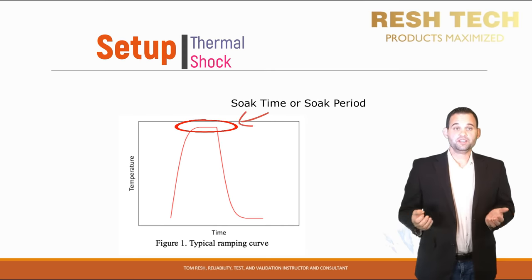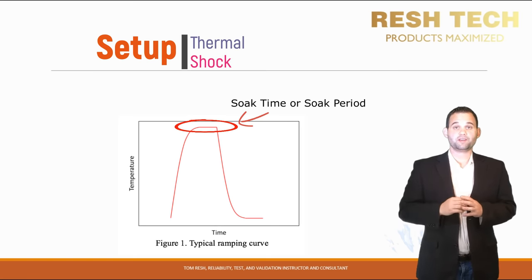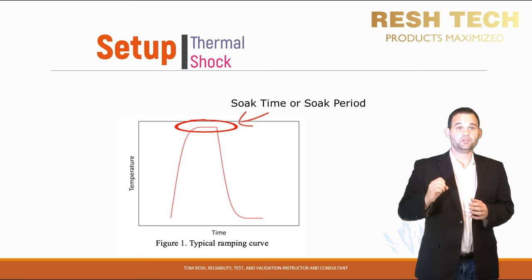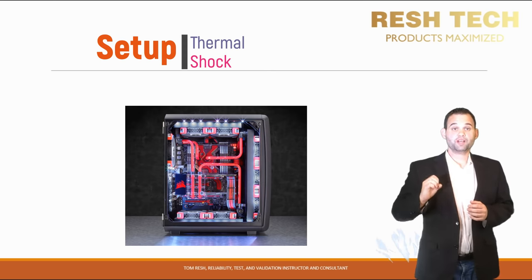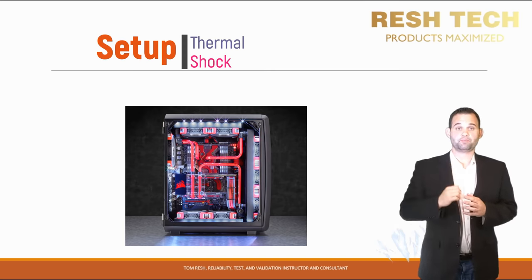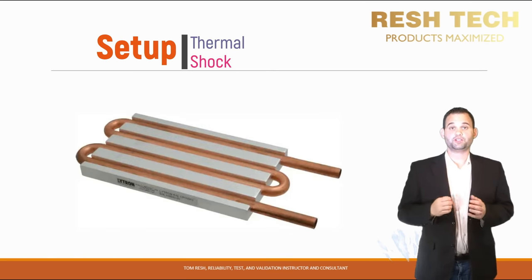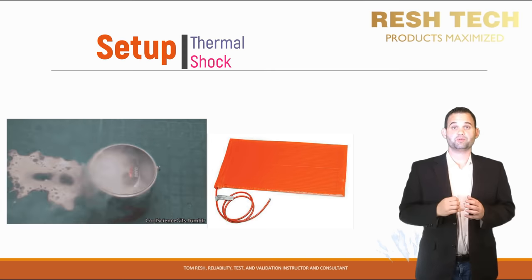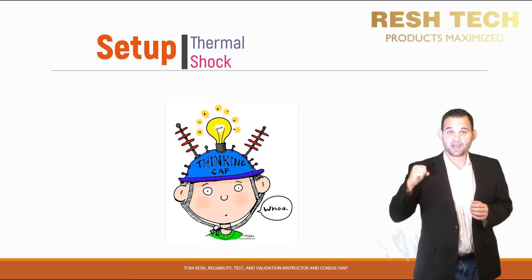Let's talk about soak times. You need to soak your system long enough for it to achieve thermal equilibrium. This can be less than an hour for small systems or parts, but can take hours or even days for larger systems. For larger systems, try to be creative in reducing soak times — such as identifying features like active cooling that can be leveraged. For instance, if you have a liquid-cooled system, you can run higher and lower temperatures that match the chamber set points and speed up the change of temperature to reach thermal equilibrium. You can also get creative with cold plates, hot plates, liquid nitrogen, or heating blankets to speed up thermal shock testing.